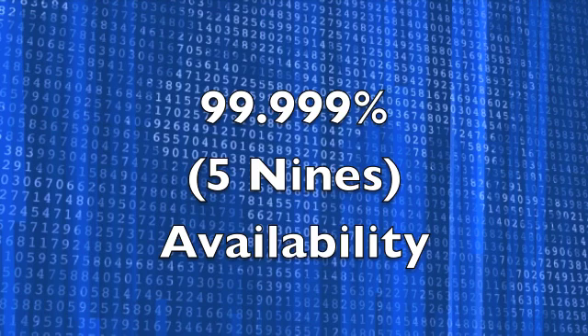In other words, how much of the time is this particular device available? Availability includes how often it breaks and then how fast it gets put back into service. You also have to include how often it's out of service or unavailable due to routine maintenance.